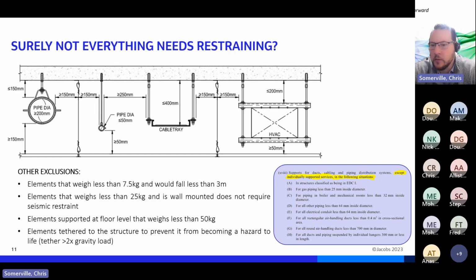Pipe is also a key one. If you've got pipes that are quite heavy, try to keep them up to the structure, because even if you can't stay within the 150, it'll make the seismic restraint much simpler. They can cause quite a lot of challenges down the road. And ducting as well - ducting within 200 mil doesn't need restraint.